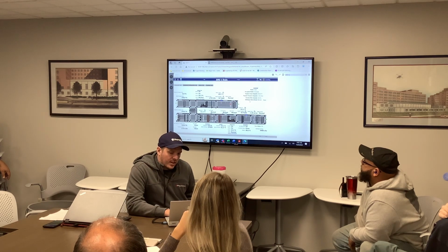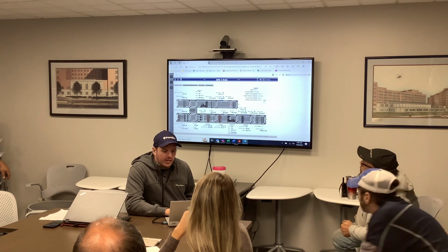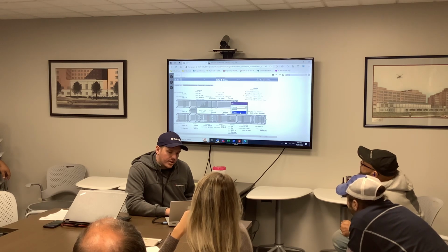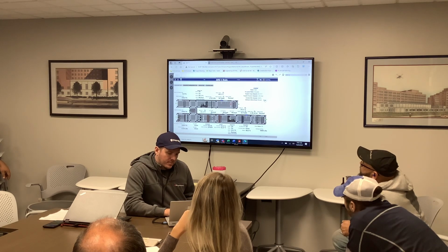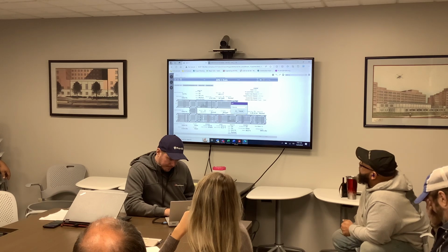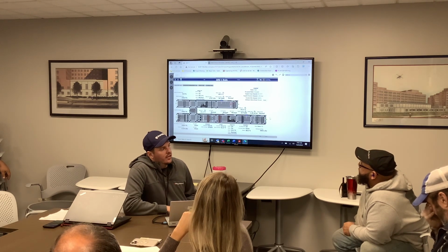This last thing is a software alarm reset. So if you see under a supply fan, it's gonna tell you it's an alarm and it's locked out. And how you clear that alarm is you come up here and you hit reset, and then you put it to reset or trigger, and then it's gonna clear any alarms. It has no alarms right now, so you're good. You have to put it back to normal after you do that? You don't have to, but you'll have to cycle it if it alarms again.